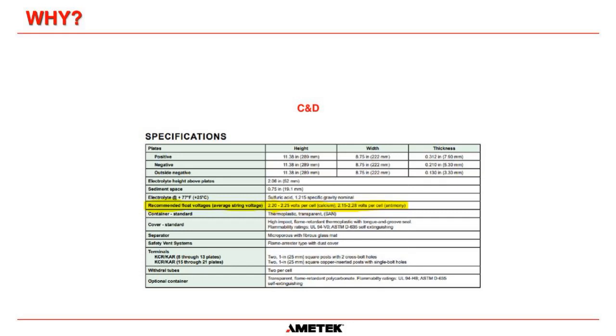Another question. What is a typical life cycle expectation on a UPS system? That completely is down to the manufacturer of that UPS. Our UPSs are designed for a 20-year life cycle, because we oversize everything and we really build robust UPS systems. If you buy a commercial system, it could be between 5 and 8 years.